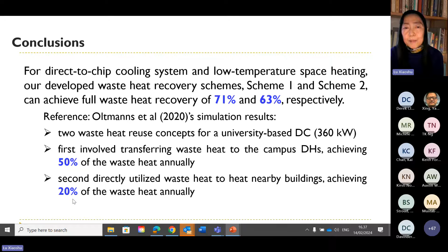Here I show a reference from existing literature published in 2020. Because capacities are different, direct comparison is not straightforward, but nevertheless you can use it as a reference. This simulation result uses a waste heat reuse concept based on a university-based data center with IT capacity of 360 kilowatts. One method uses waste heat for the campus district heating system, and the other heats nearby buildings.